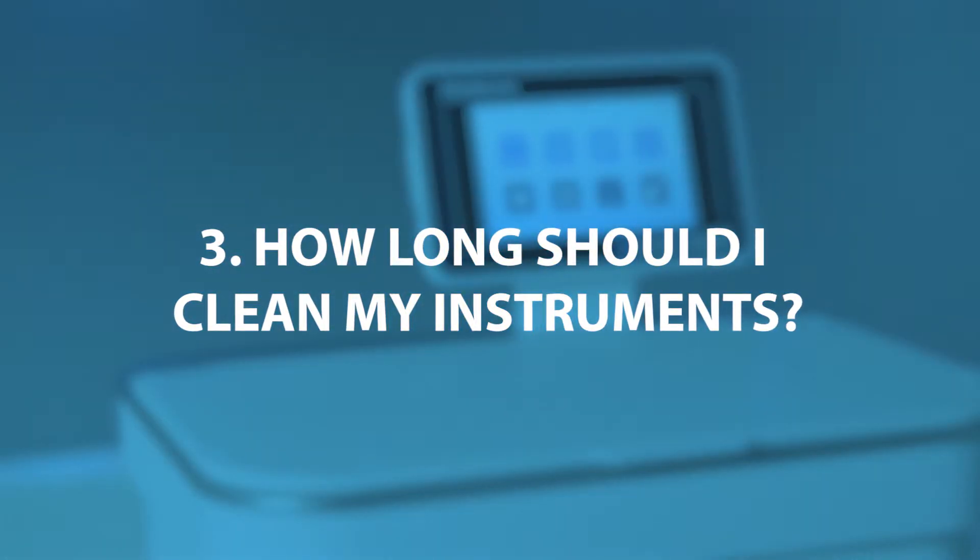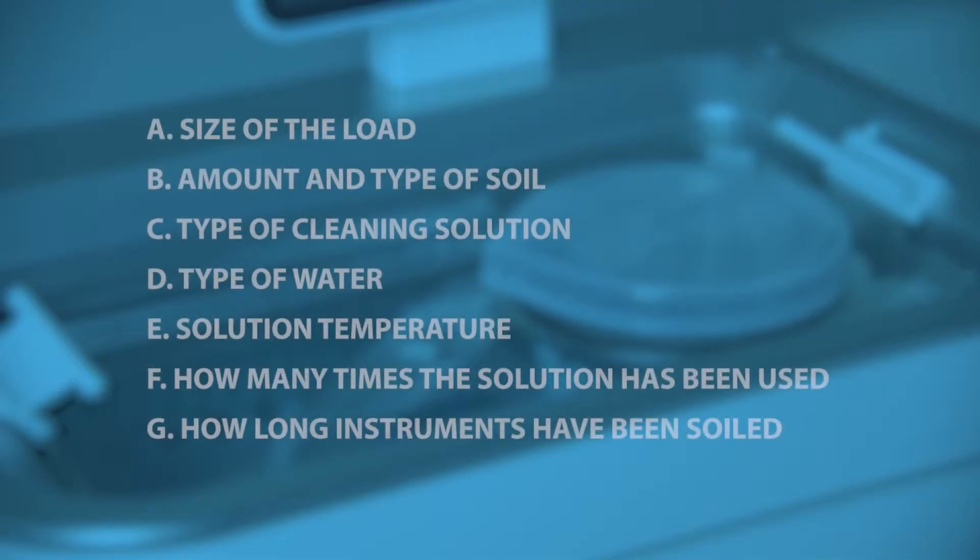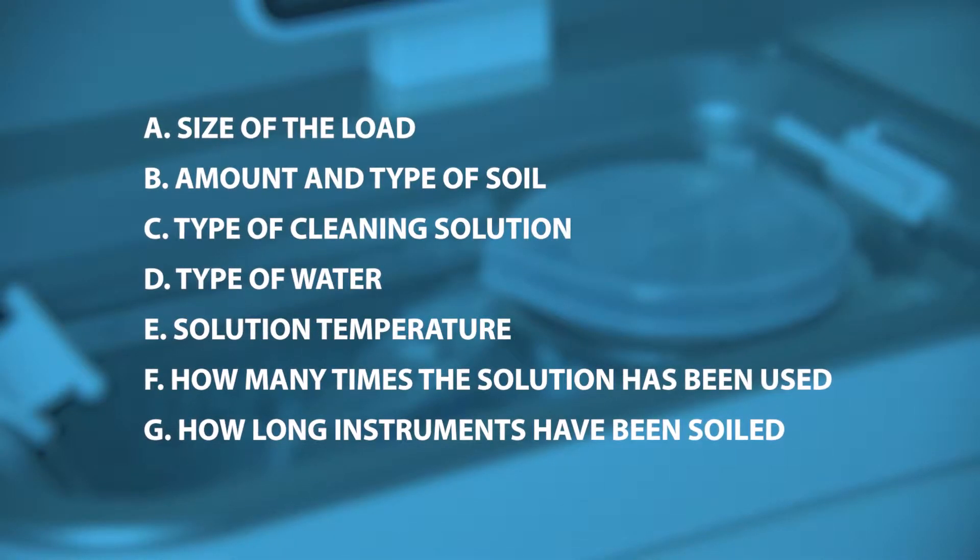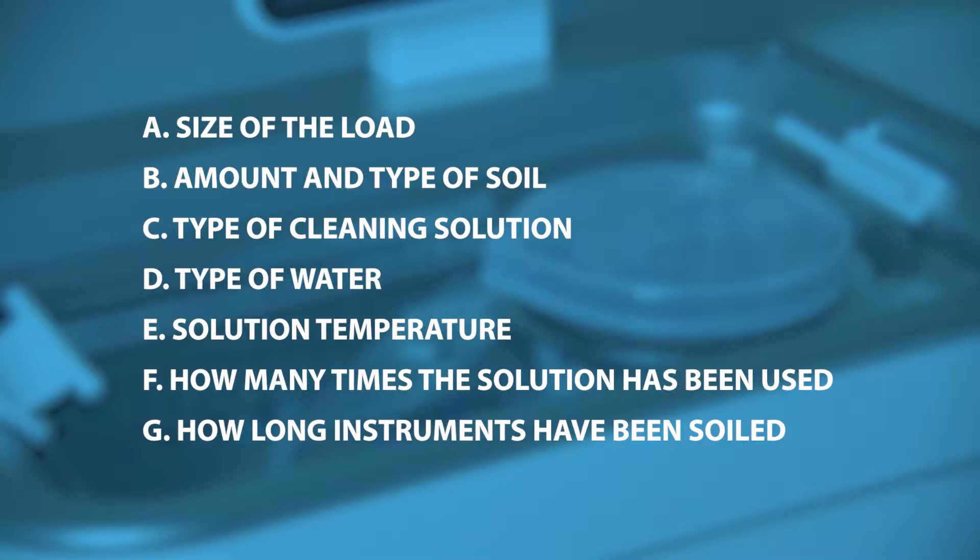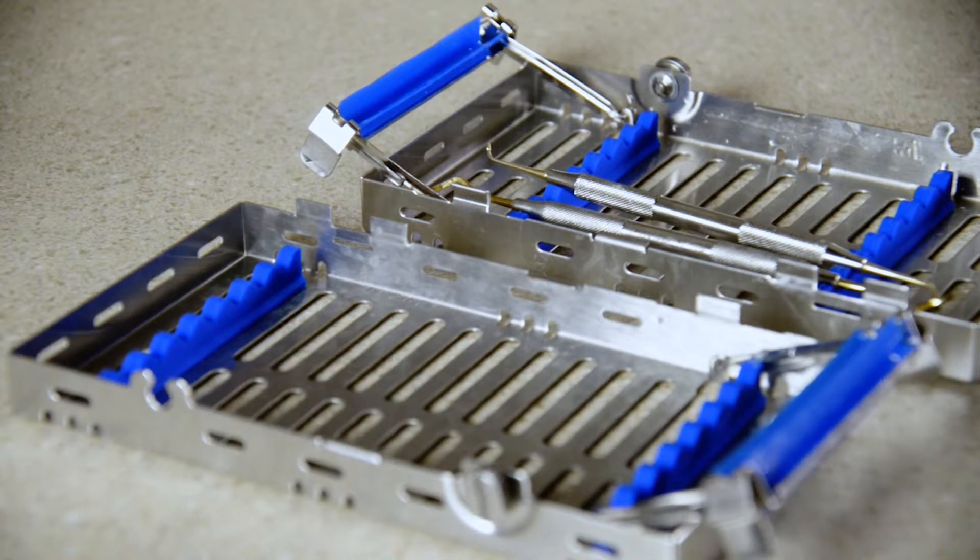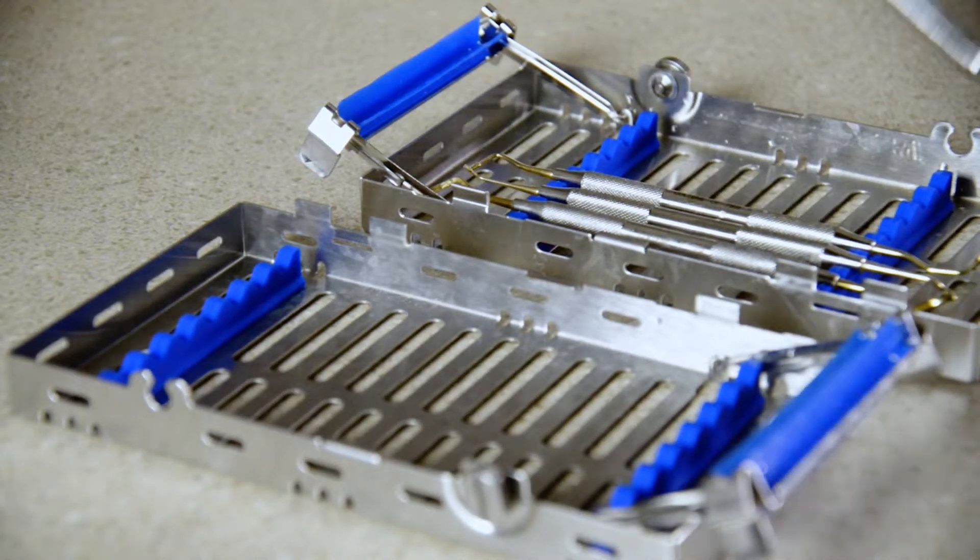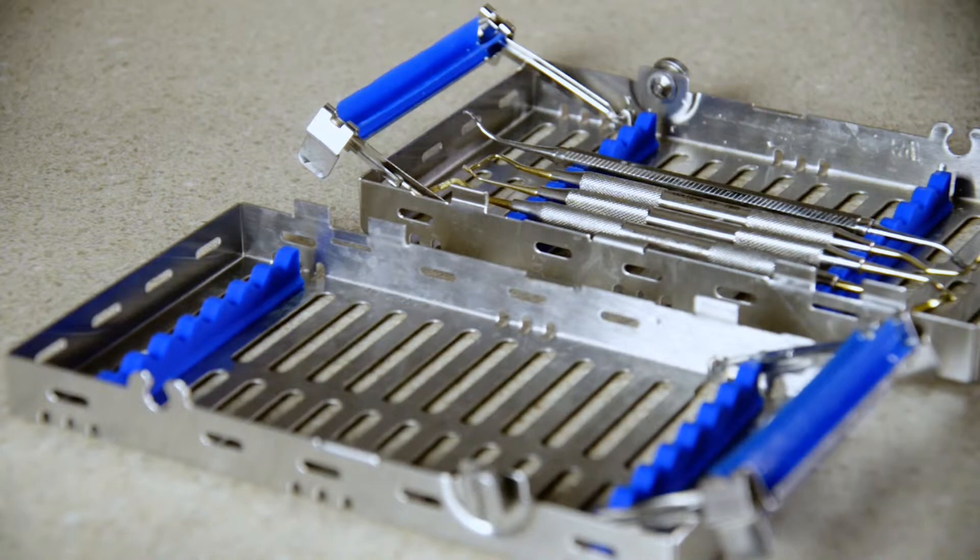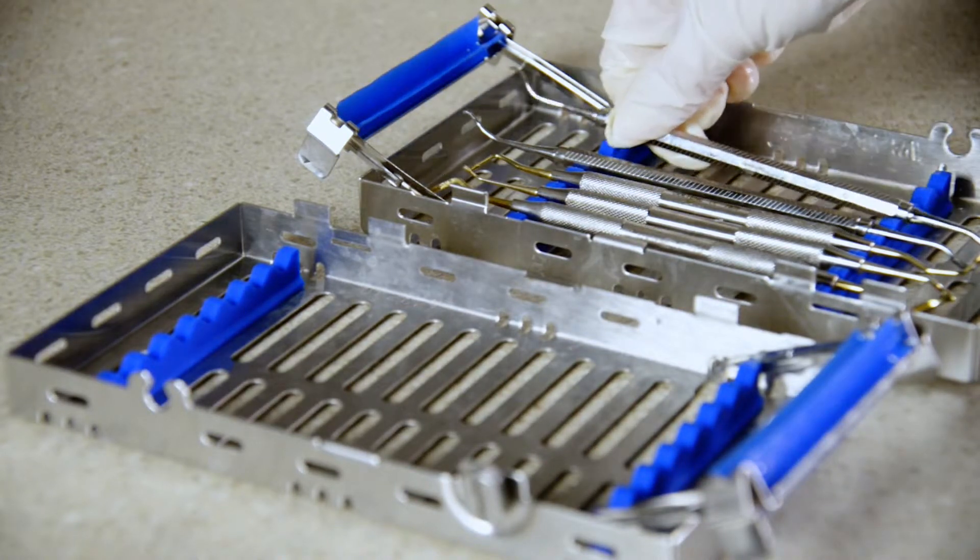How long should I clean my instruments? There are several parameters to consider when determining the duration of any cleaning cycle. Size of the load being cleaned. The more instruments placed into an ultrasonic bath, the less effective the cleaning cycle will be. A larger load will require a longer cleaning cycle.